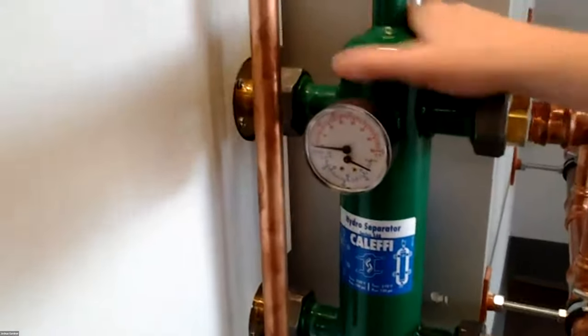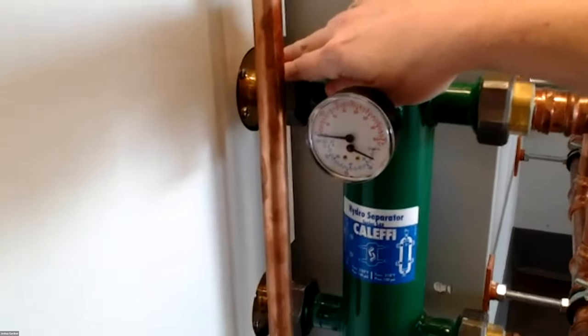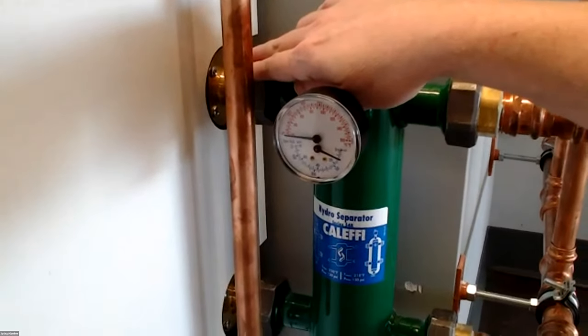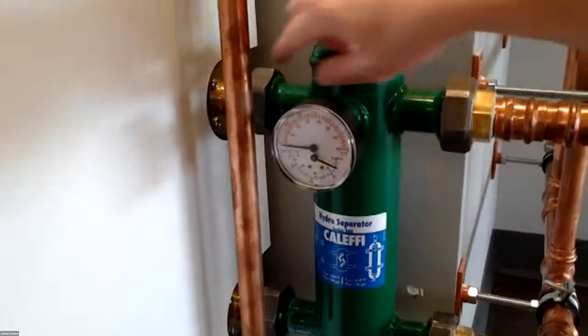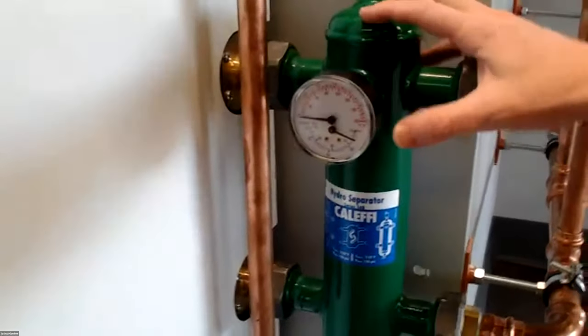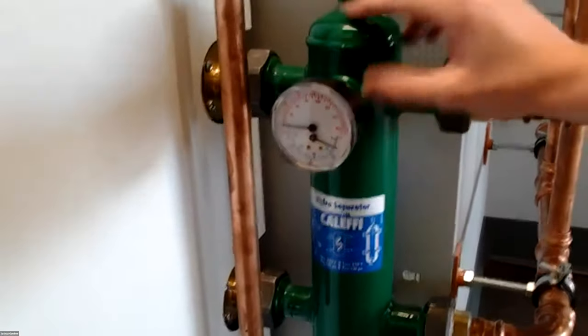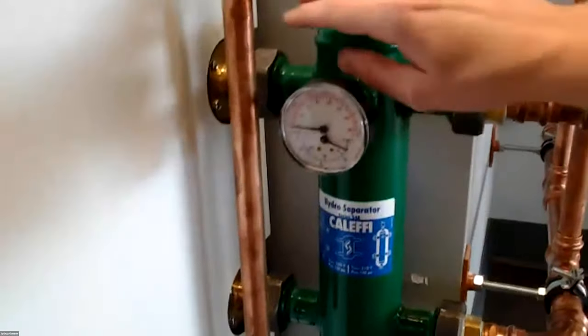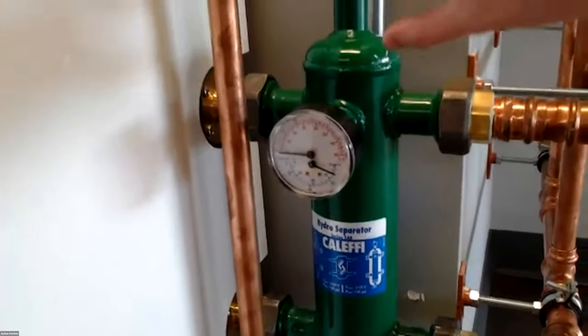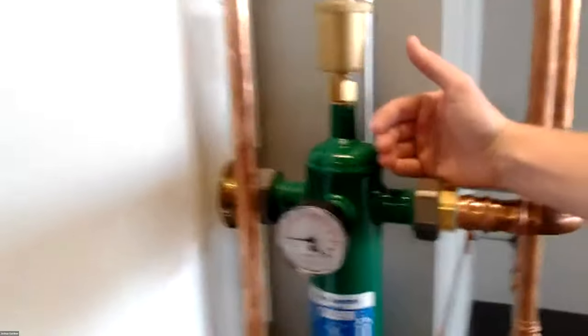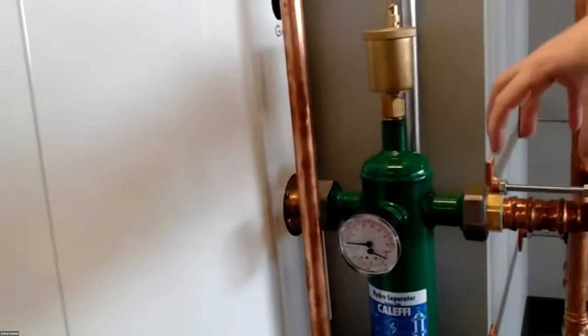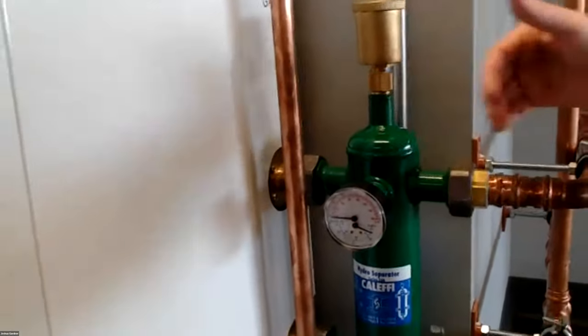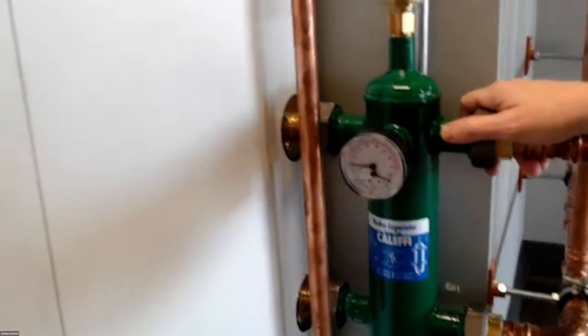One thing to note, the 1-inch will bolt directly on here. The 110 and 155. If we're using the 199, there's going to be some offset adapters because the 199 low loss header is a lot bigger than this one. It's taller, spaced out differently. So there'll be offset adapters. That low loss header on the 1.25 will actually probably stick out about right here. So you'll have a little bit more room out there that you'll have to watch out for.